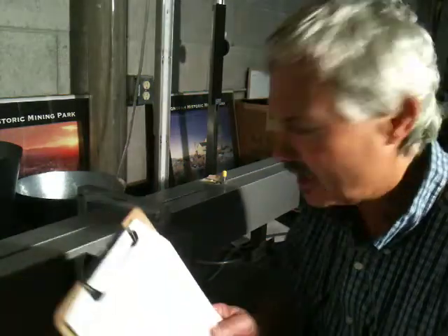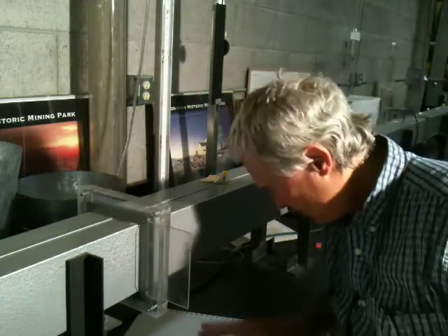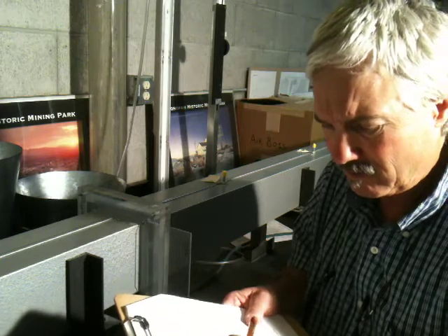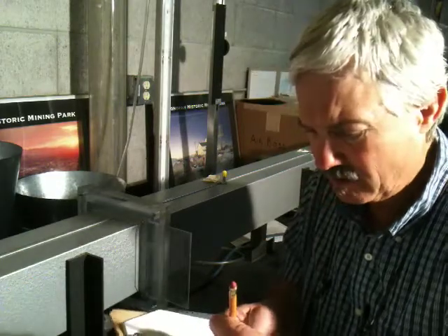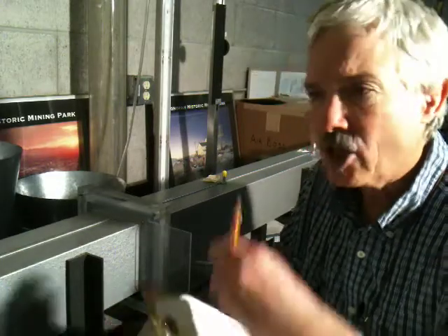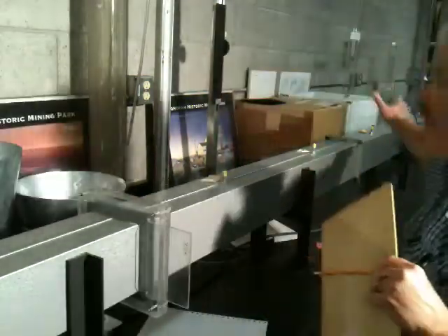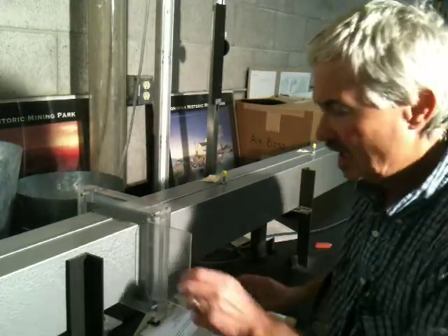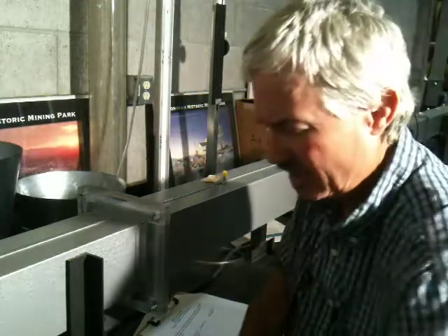Now the velocity pressure for the 3 3/4 regulator size was 0.832 inches. And in this case, delta static pressure is 1.157 inches. So again, that's the pressure drop between the upstream side of the regulator and the downstream side of the regulator. Okay, that's 3 3/4. Now we'll put in the 3.5 inch square regulator.